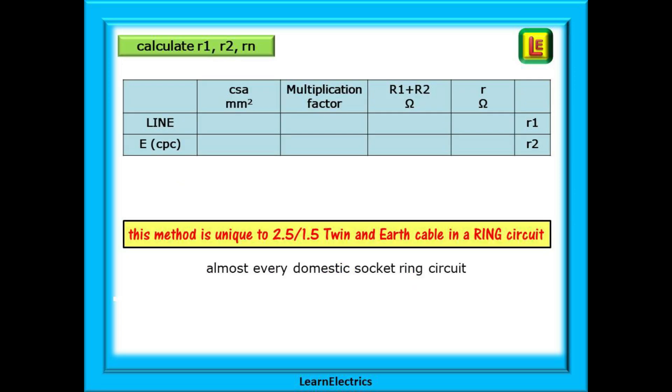Okay, let's calculate little R1. I've shown here a table as a way of making it easier to understand the process. This method is unique to 2.5 twin and earth with a 1.5 CPC and this will cover 99% of households, almost every domestic socket ring circuit in the UK.